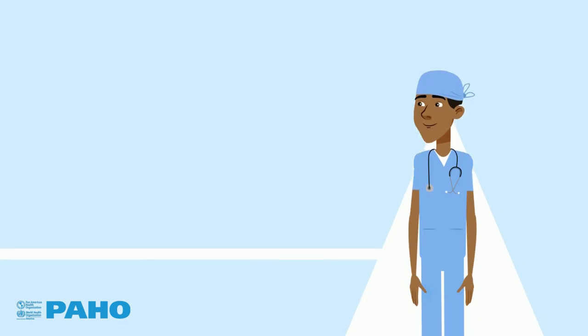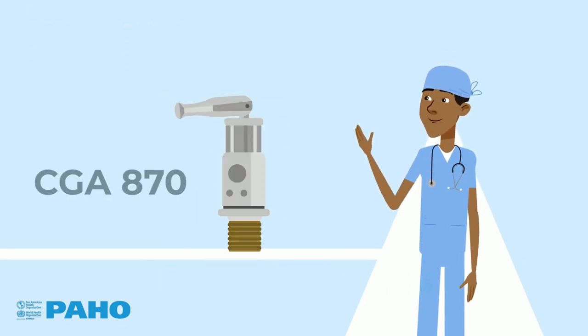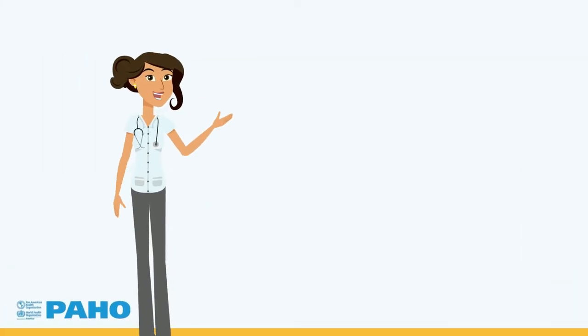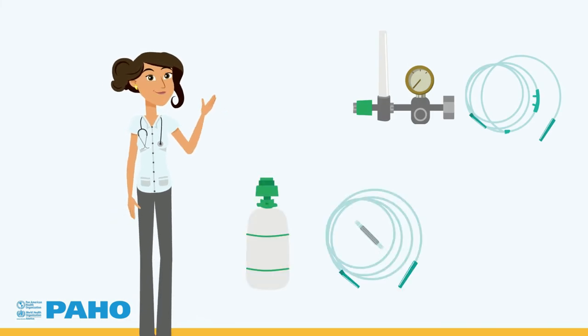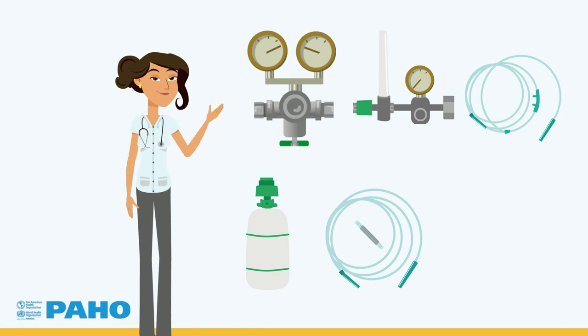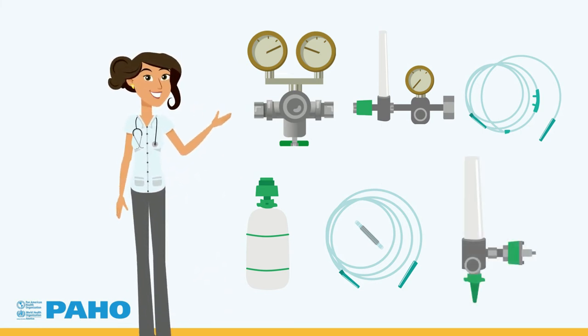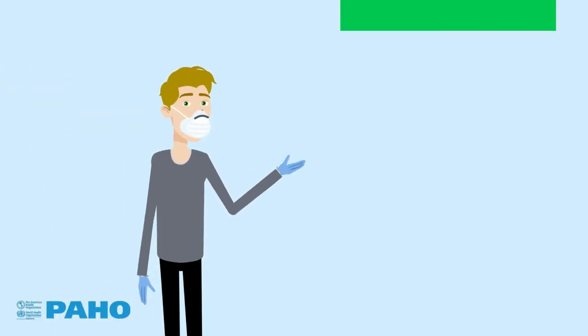There are several types of valves. CGA 540 and CGA 870 are the most common in our region. Because this valve determines the types of accessories that a healthcare facility requires, it is reasonable to standardize this item. Doing so makes it possible to avoid duplication of connections and devices within an organization, and facilitates monitoring. This information must appear on your purchase order.